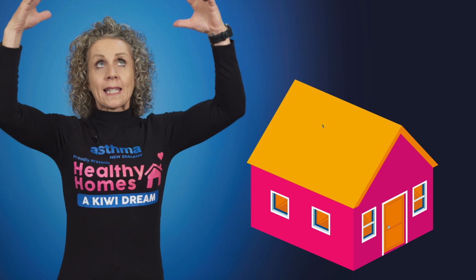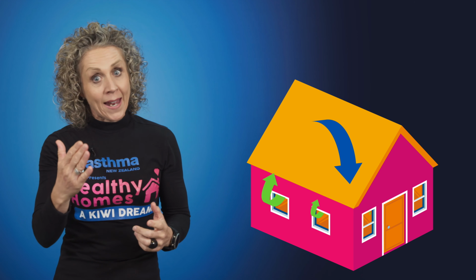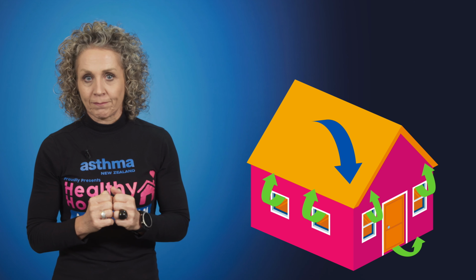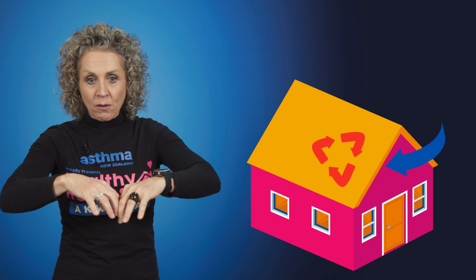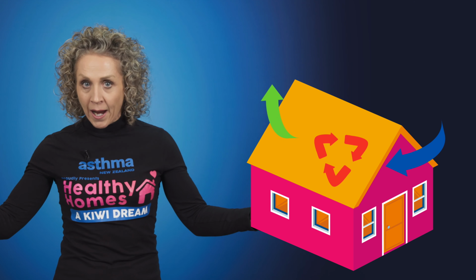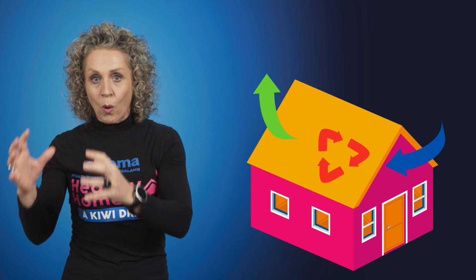So I think I understand the difference between positive and balanced ventilation. Let me see. Positive ventilation takes air from the ceiling cavity and pushes it into the house. That's its job. In order for that air to go out, it has to find its own way out. Whereas balanced ventilation takes air from the outside and brings it into the house, but it also takes air from the inside and takes it out of the house. So it balances up the flow in a controlled way.